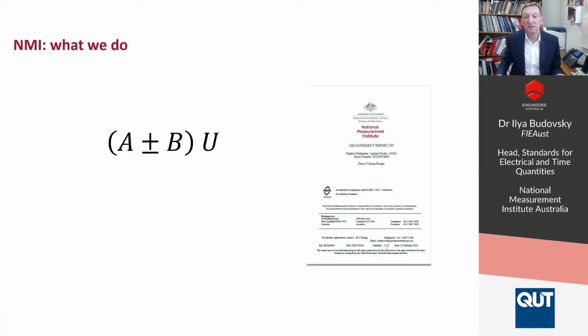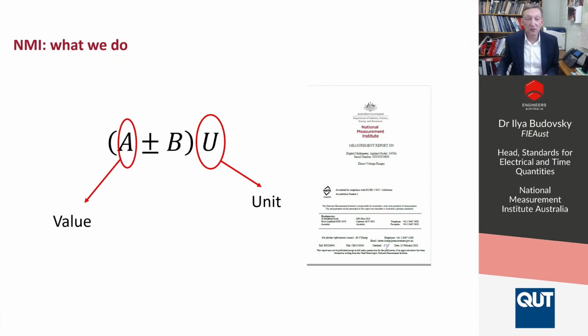In very simple terms, in relation to the matter of discussion here, when we measure something, we do it in terms of units, and we provide a value. We all do. And very importantly, for a traceable measurement, we need to provide an uncertainty. The uncertainty is stated in the calibration report, and very large efforts go into ensuring that the value lies within the uncertainty.